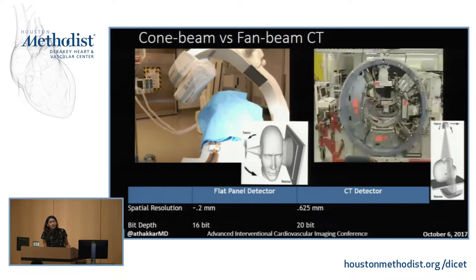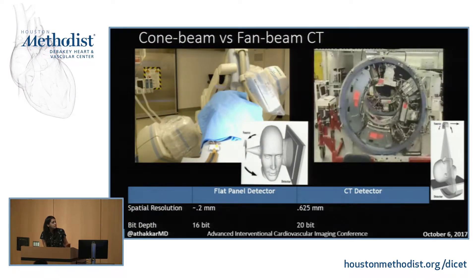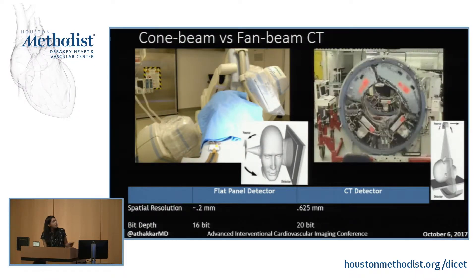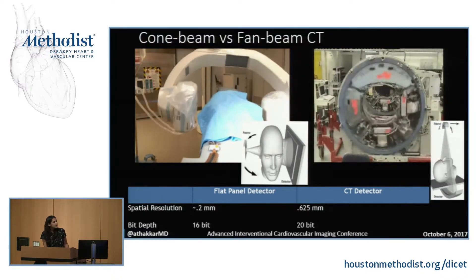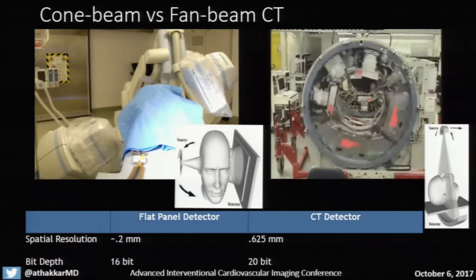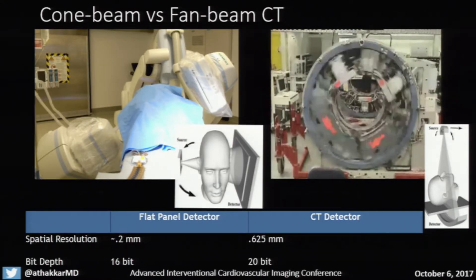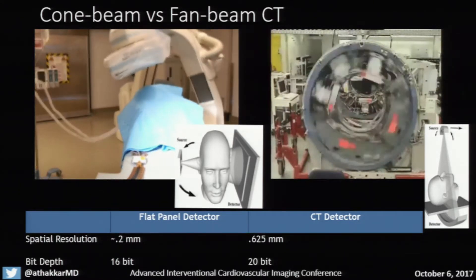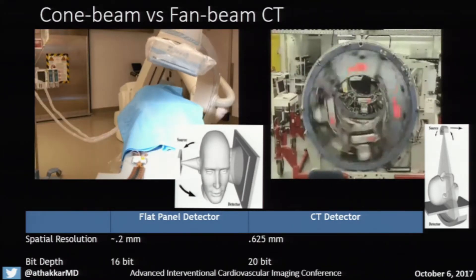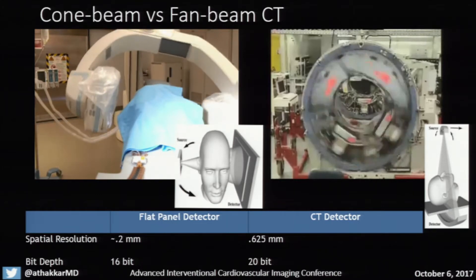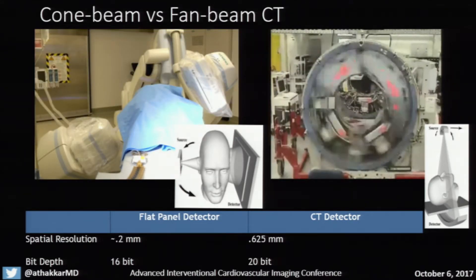A side note about cone beam CT: it is integrated with 2D fluoroscopy and does differ from regular CT in the geometry of the X-ray beam used to acquire images, and also in image quality. Basically, with the cone beam CT, the image quality is not as nice as with your regular dual-source MDCT.